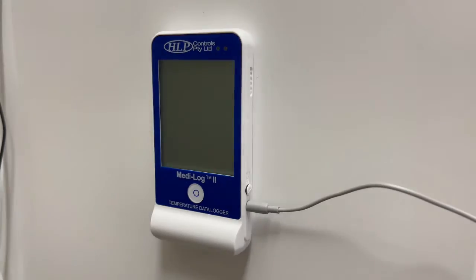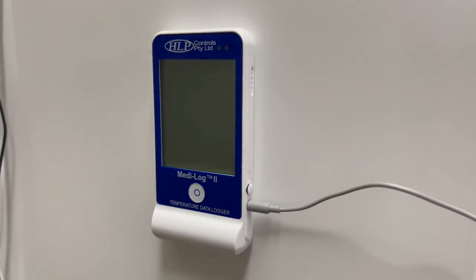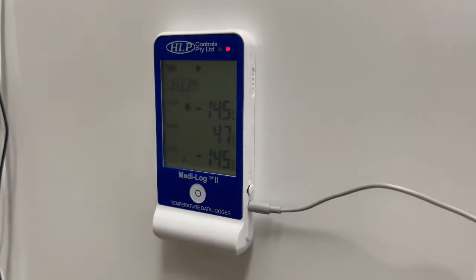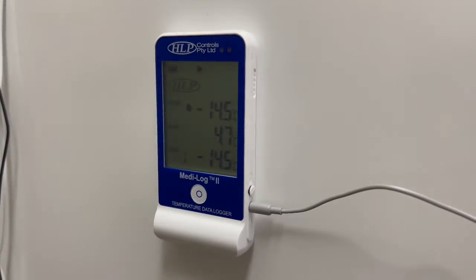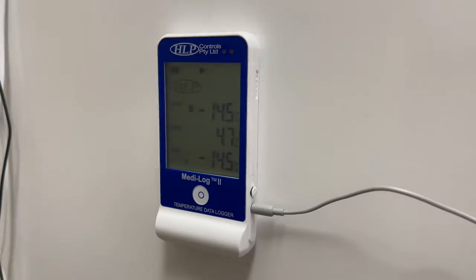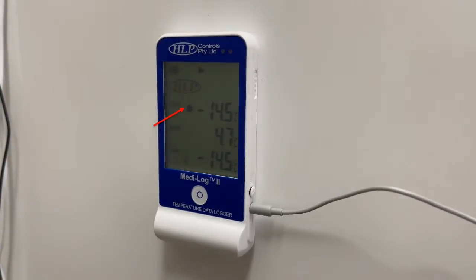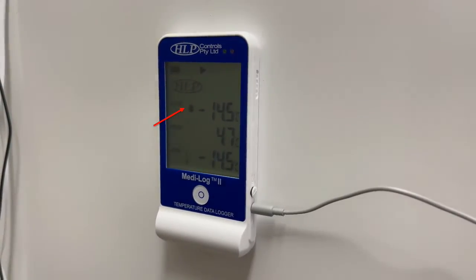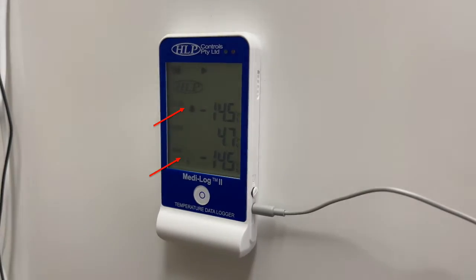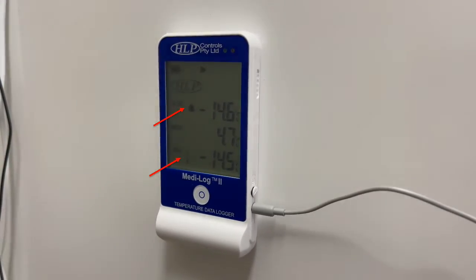In case of unit alarming. When the probe reaches a temperature outside of the predefined limits, the unit will initially sound a 3-beep audible alarm, whilst also displaying the min-max alarm page. A bell icon will be displayed to represent the alarm being active, and there will be an arrow icon next to either the min or max display to indicate what limit has been exceeded.